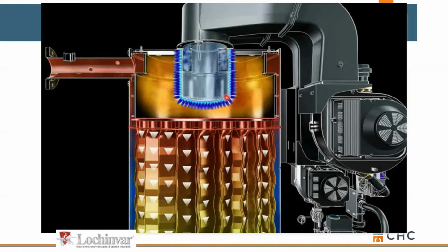More commonly, now what they've done is they've just gone with a single blower. They still have 2 gas valves, and they use something almost like a butterfly valve. They call it an air damper, but the air damper stays closed for the first section of their burner, and then it opens to allow more airflow to fire the whole heat exchanger, or the whole burner in this case.